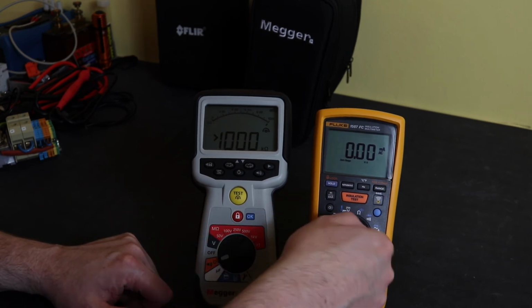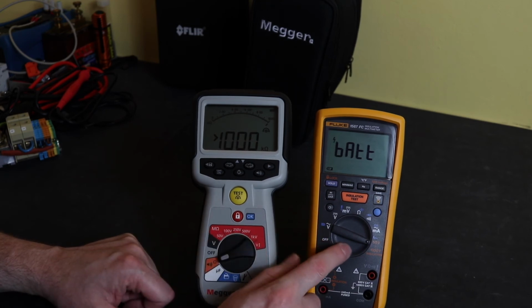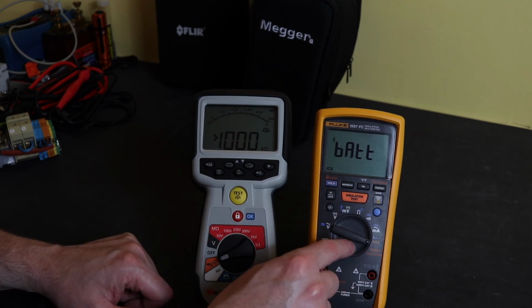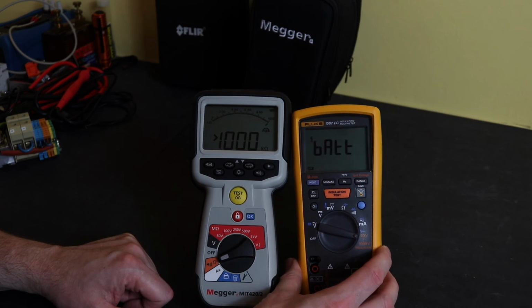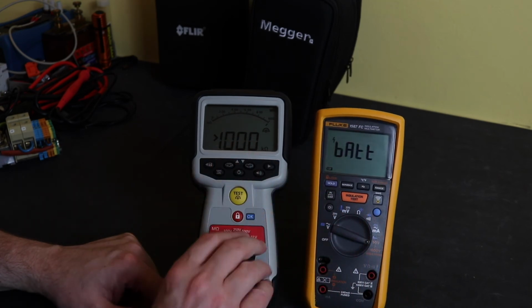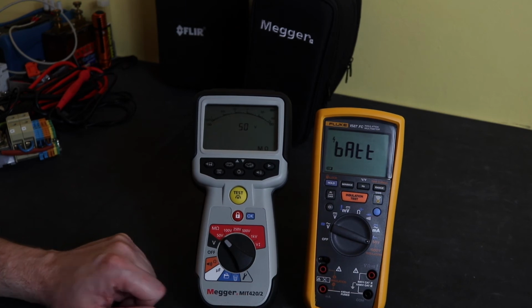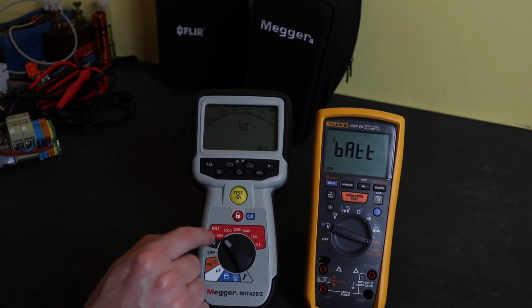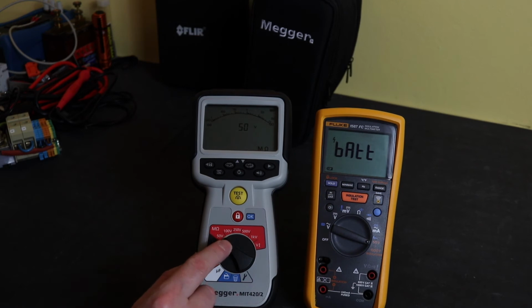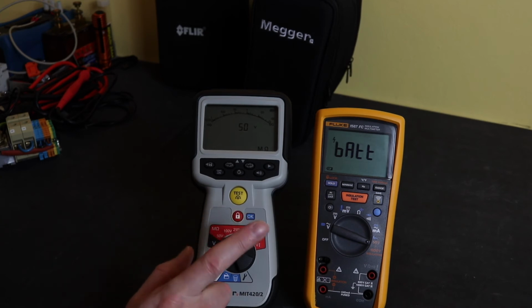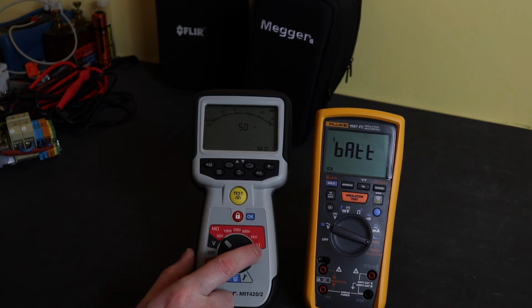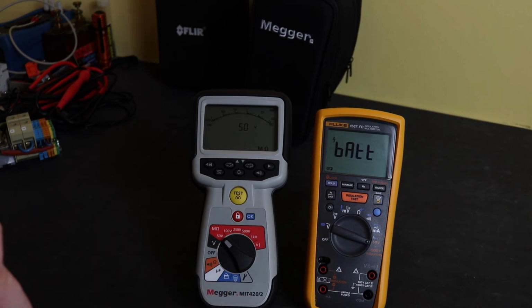And then the final position on the function switch on the Fluke here is the insulation test and another low battery. Damn, this thing's eating batteries. So on the Megger, the insulation test function is on the upper part of the rotary switch. Test voltage is manually selected 50, 100, 250, 500, 1 kV, and then a variable test voltage at the end, anywhere from 10 volts up to 1000 volts that you set on the settings function down here.